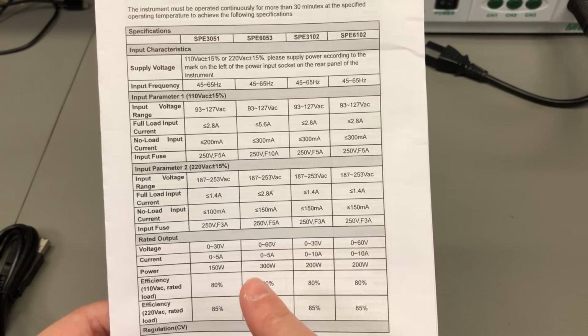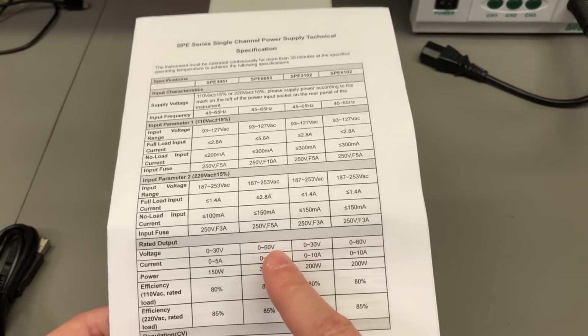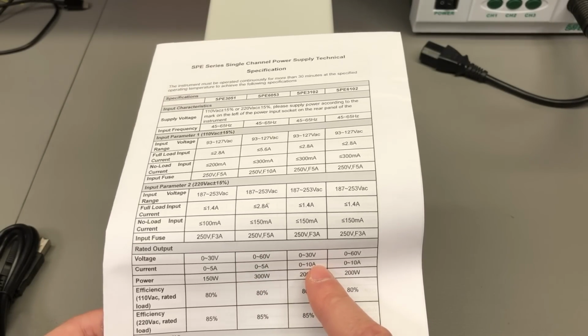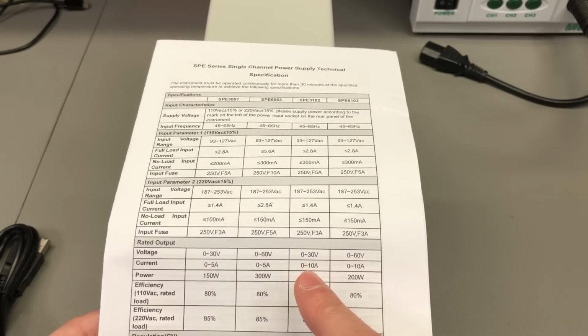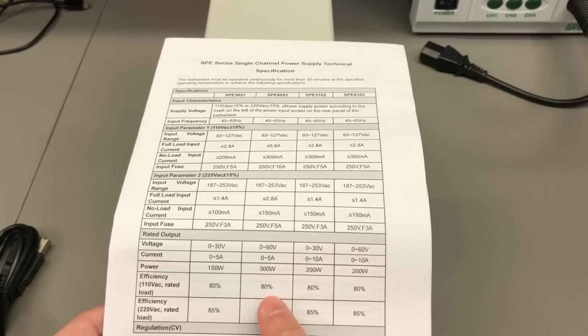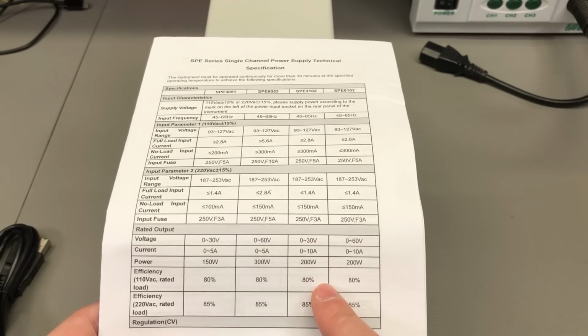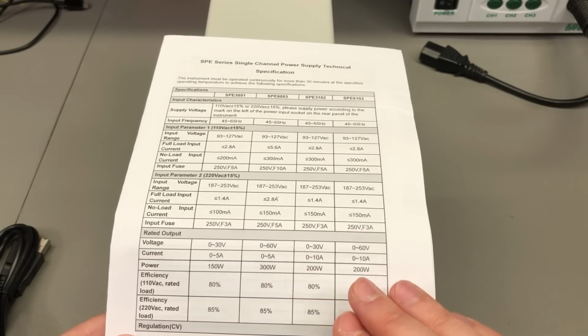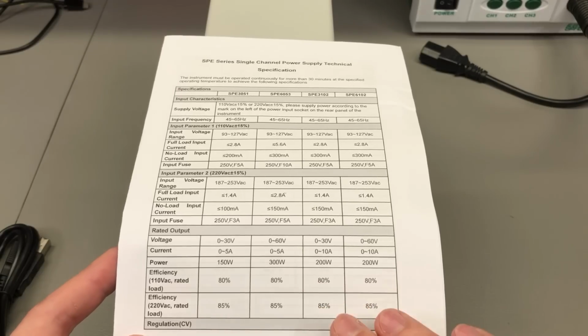You get two main output voltage ranges, 0 to 30 volts and 0 to 60 volts, with up to 5 amps or up to 10 amps depending on the model you select. But there is a catch: that doesn't mean all models can output the full power at voltage times current at the same time. That's where the different models come into play.